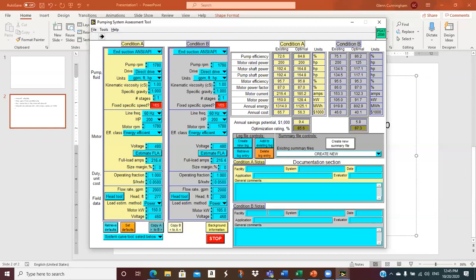So my projection would be, I would be saving about 45 kW. And now my cost of operation is $46,000 a year.